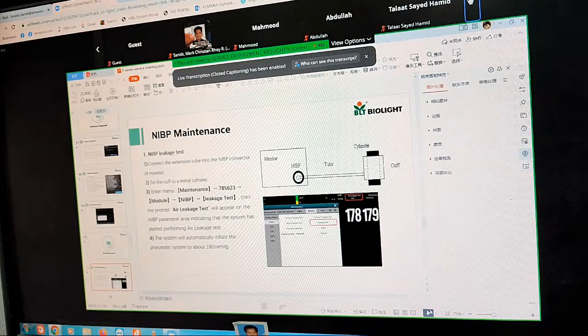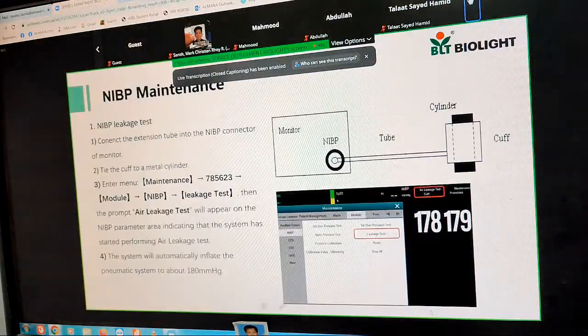Now we come back to our point, the leakage test. First, you need to connect the extension tube to the NIBP connector of the monitor and tie the cuff to the metal cylinder. Remember, it must be the metal cylinder, it can't be the other side. Then go into maintenance, put in the password, go to the module, select NIBP and choose the leakage test.